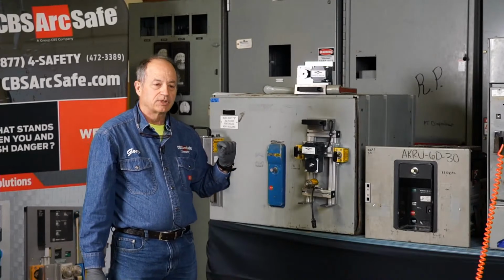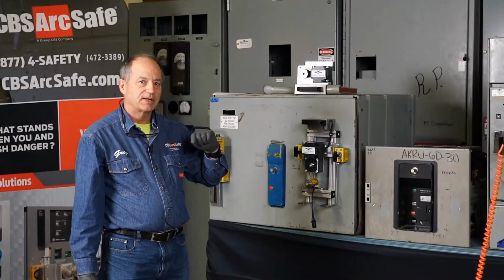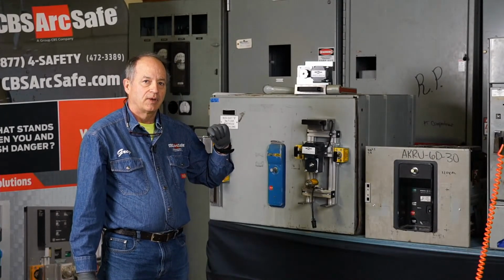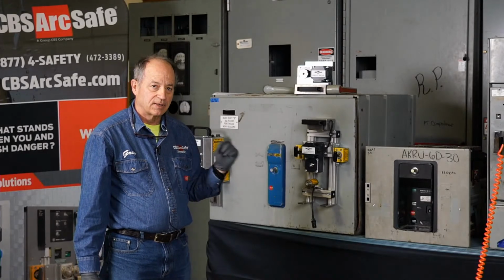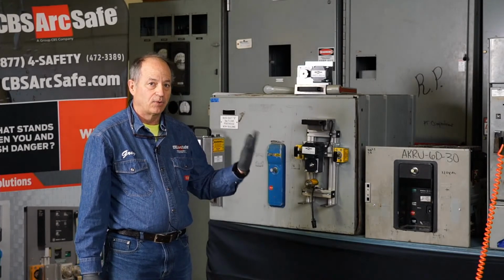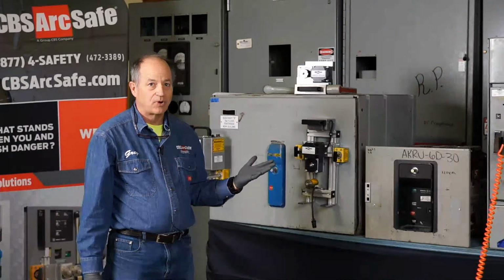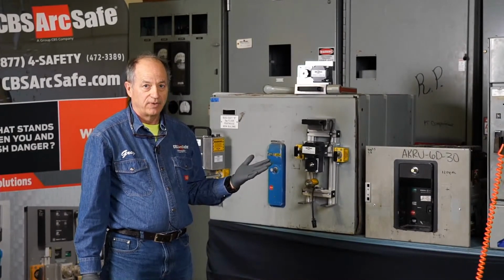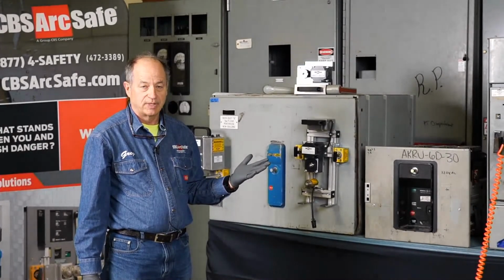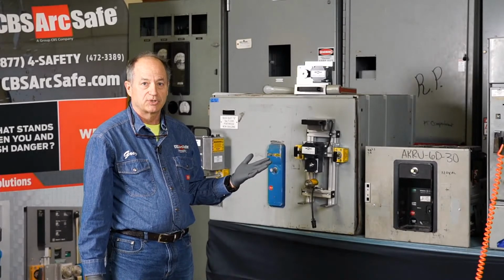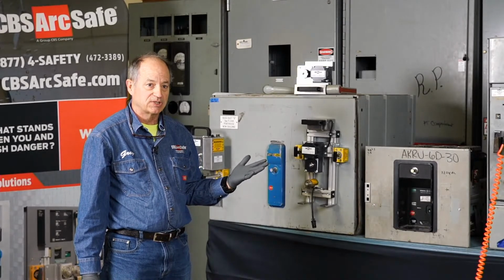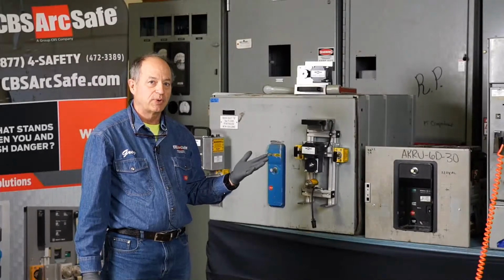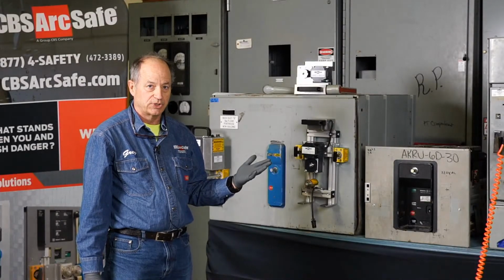Some things to note: if you see a breaker not coming off, or taking more force to take a breaker off the bus than to go on, you probably have something wrong in the switchgear. We've seen this where we've actually been given bad circuit breakers to do demonstrations on at various customer facilities, helping them identify that they do have problems with their switchgear.